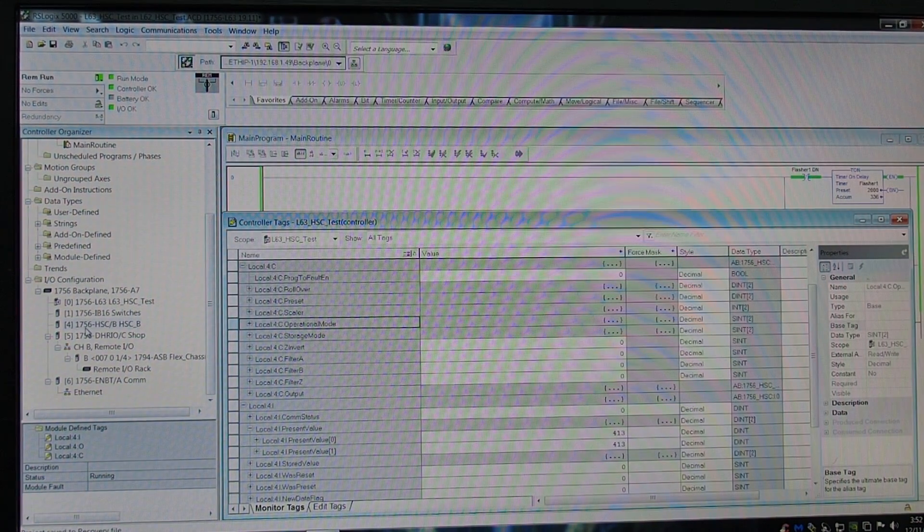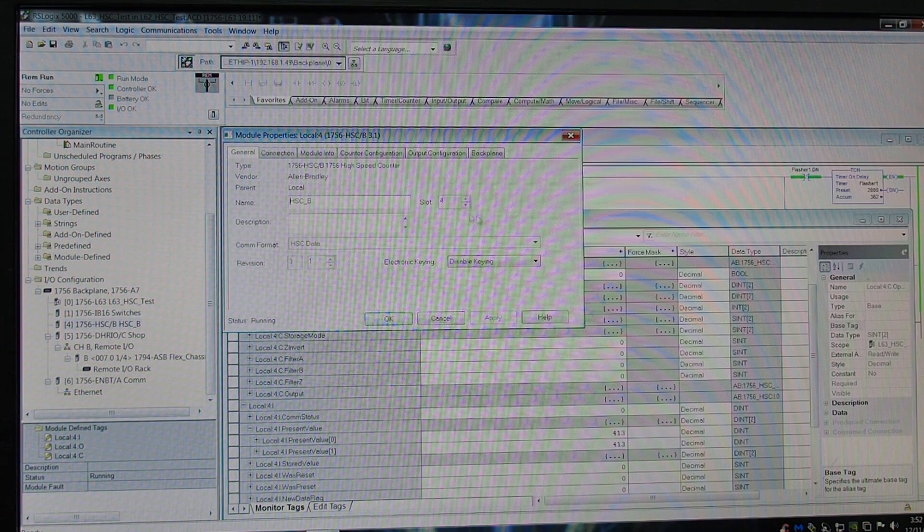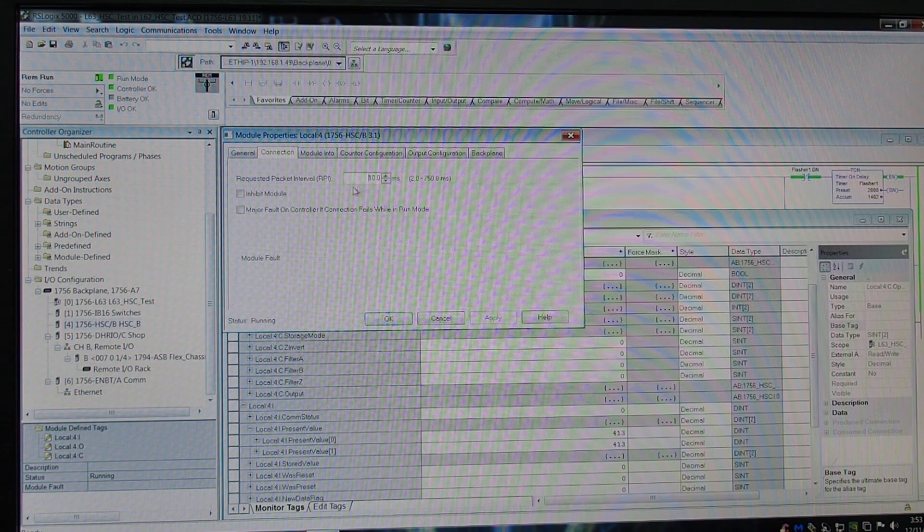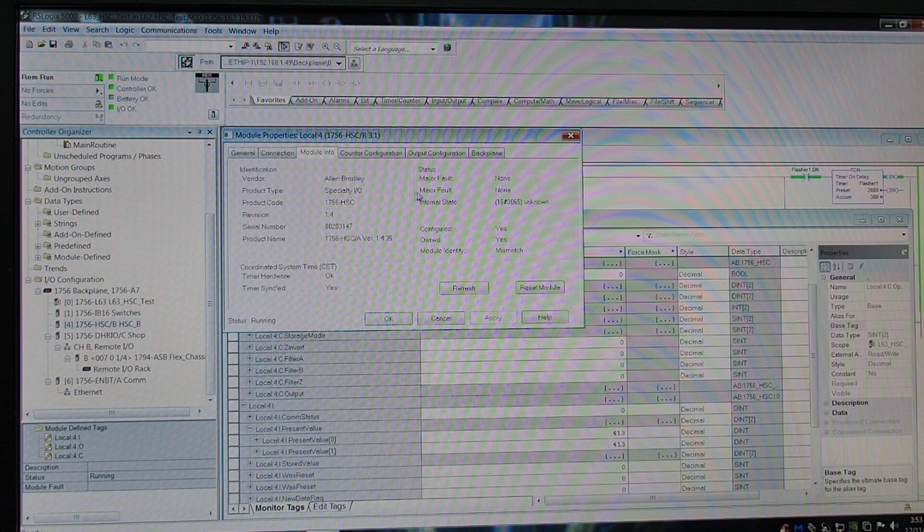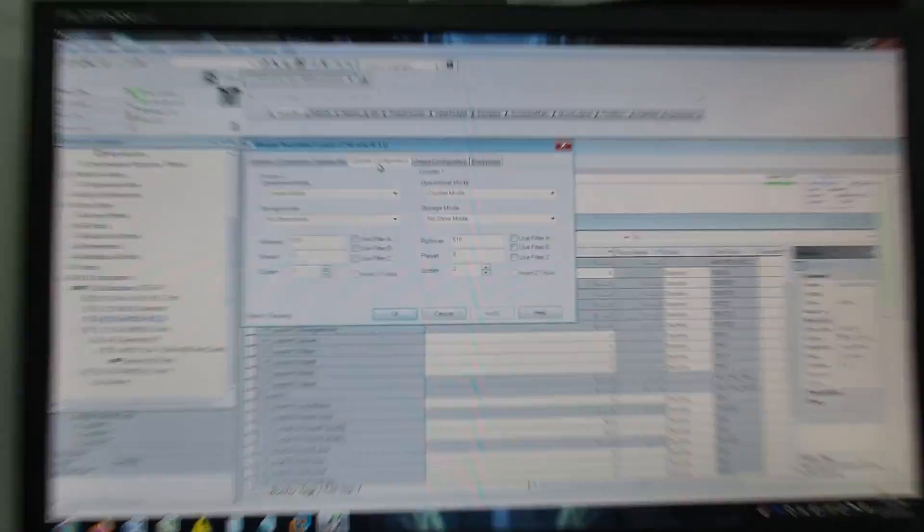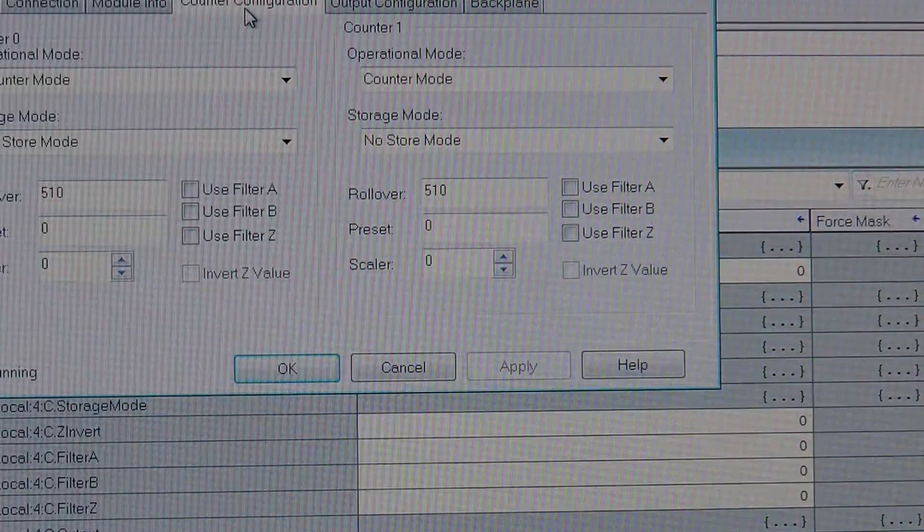So, here we are back in the computer. If we go down to here, on the left-hand side, you can see that the module is in slot four. Double-click it. It brings up the module properties box. There's our name. There's the connection. It gets a requested packet at 10 milliseconds. There's all the module info. It's version firmware 1.4. It's a series A. No faults. So, now we go to the counter configuration, which is the main one that everybody uses.